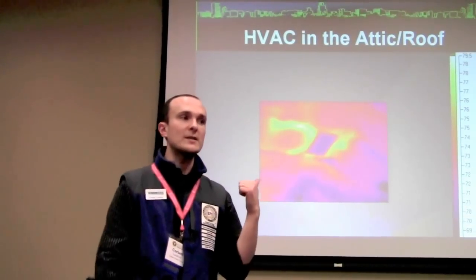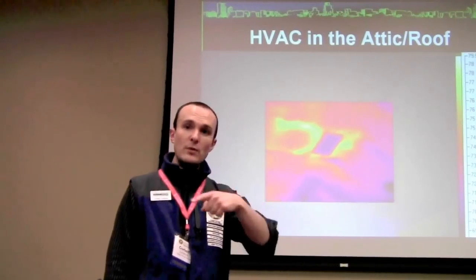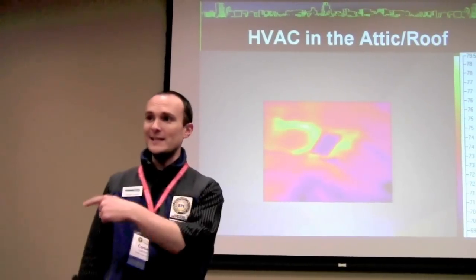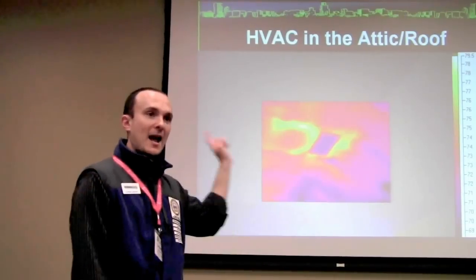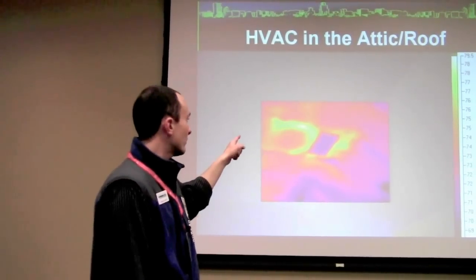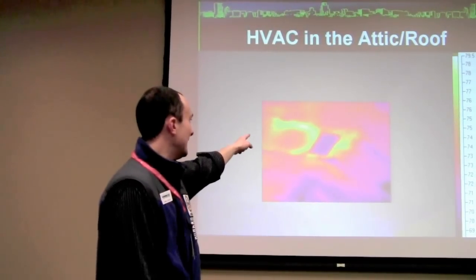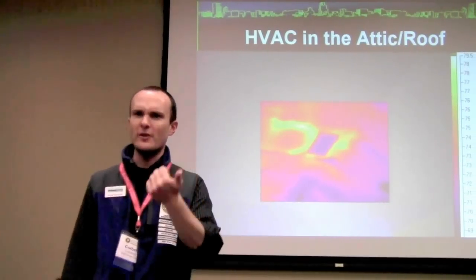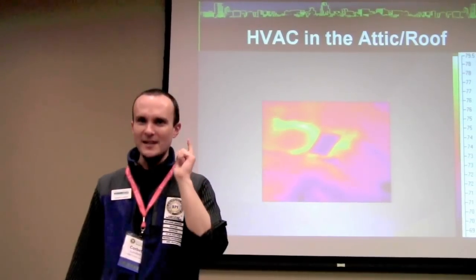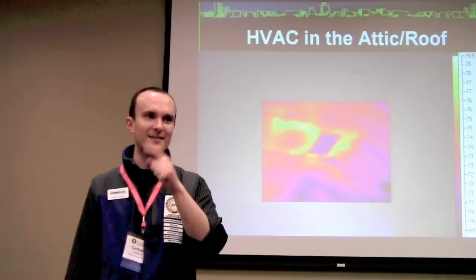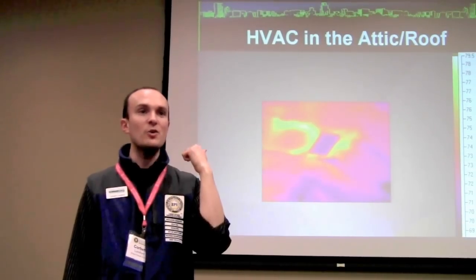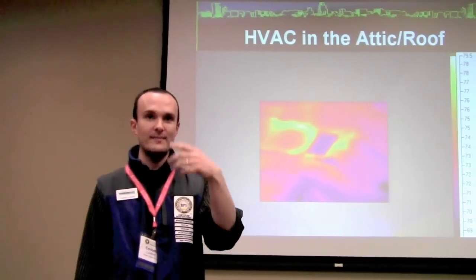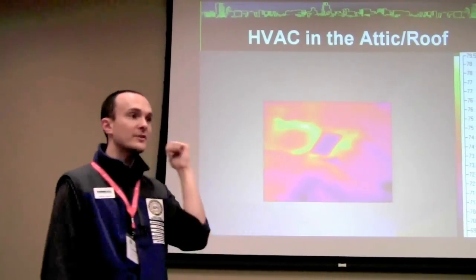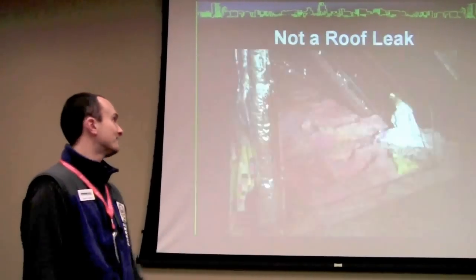I prefer it this way because when you run the furnace for the combustion testing literally 10 minutes ago, now I'm running the blower door test. Why on earth would there be cold air coming in my ductwork where the furnace was just running? I know for a fact it was 130 degrees inside that ductwork 10 minutes ago. So now that it's cold, I've just identified duct leakage, right? And that's one of the major problems at the top of the house. It's at the top, and we've got to air seal it.